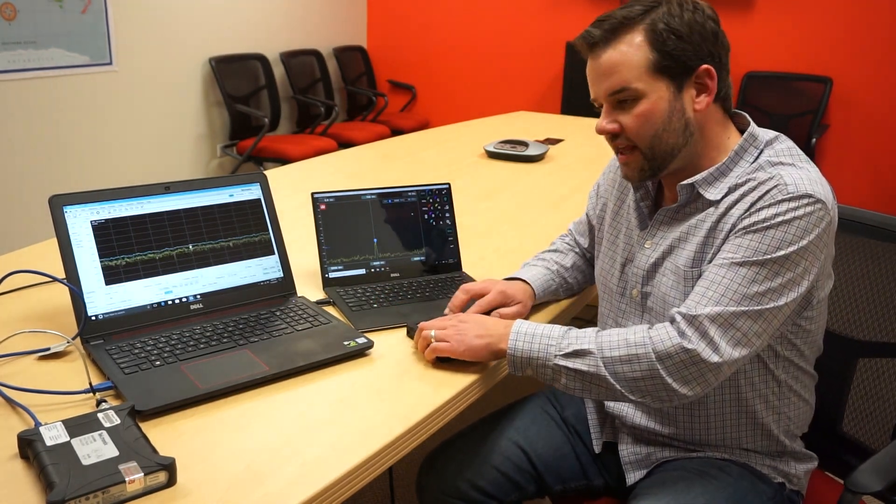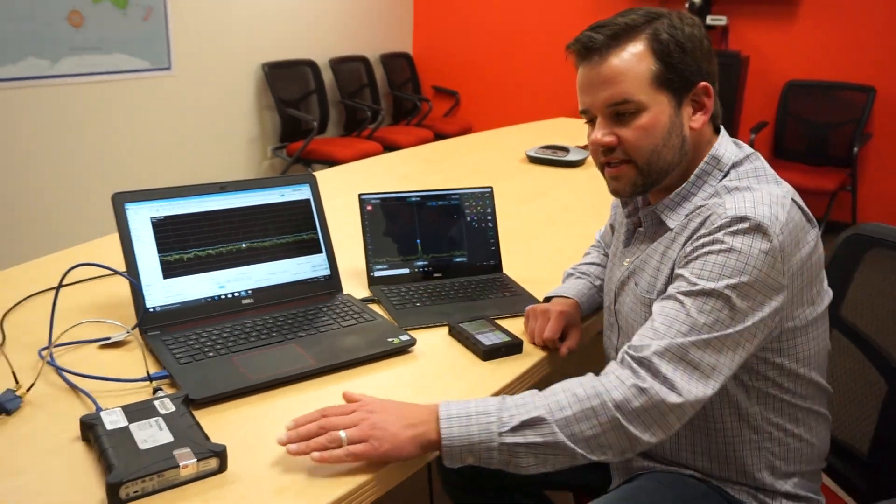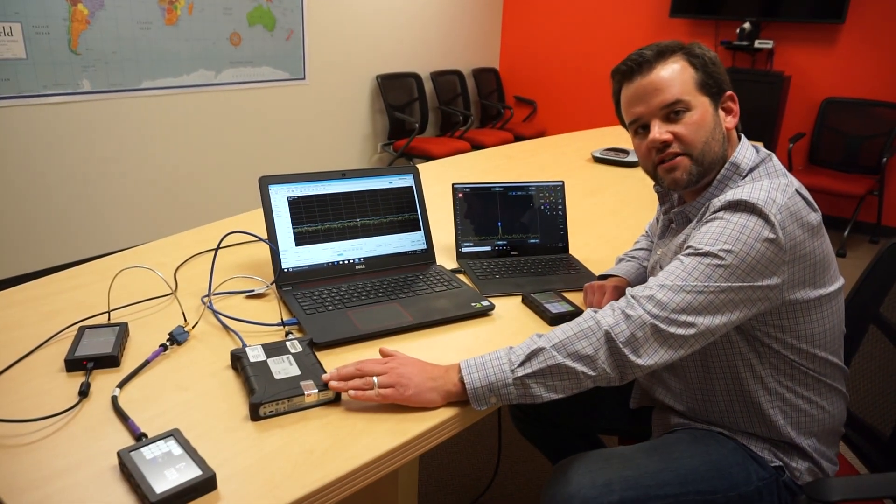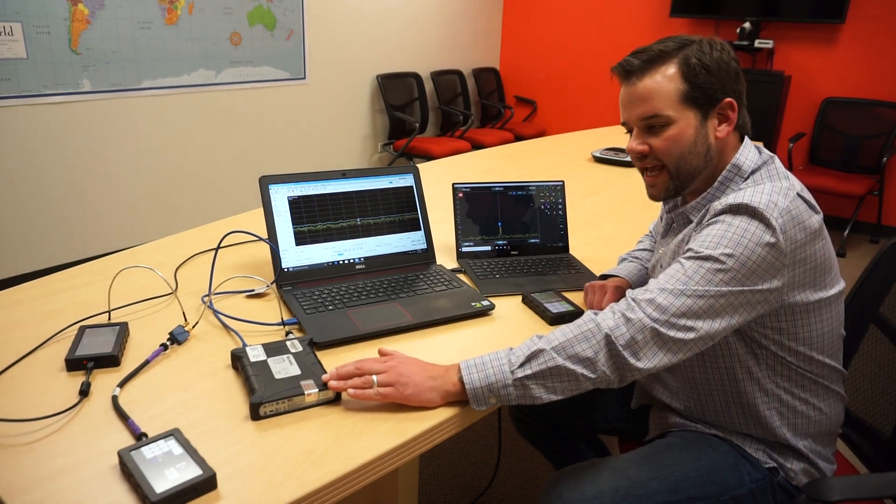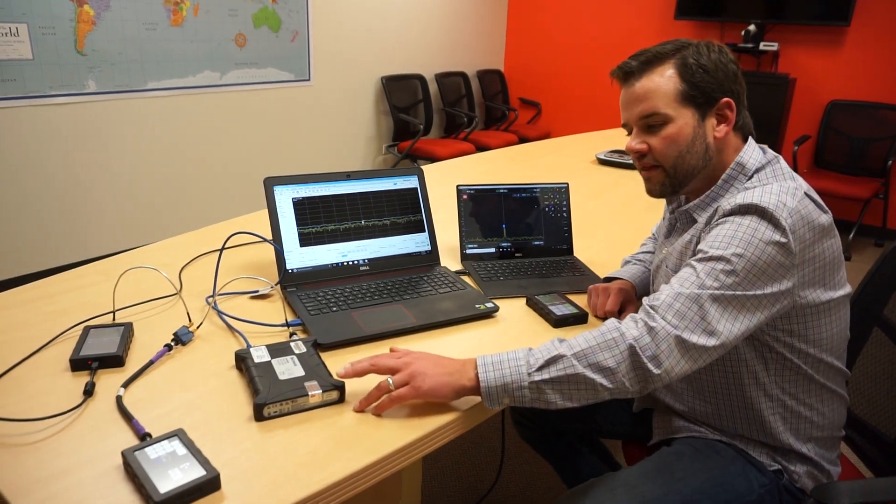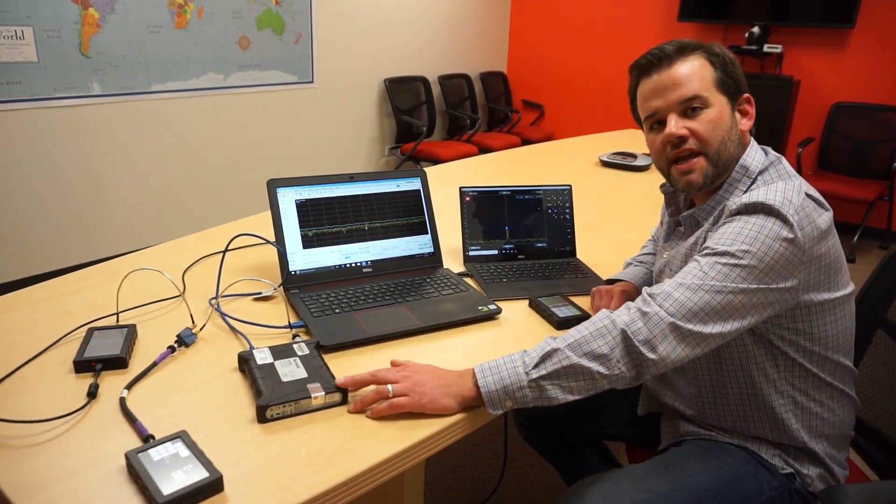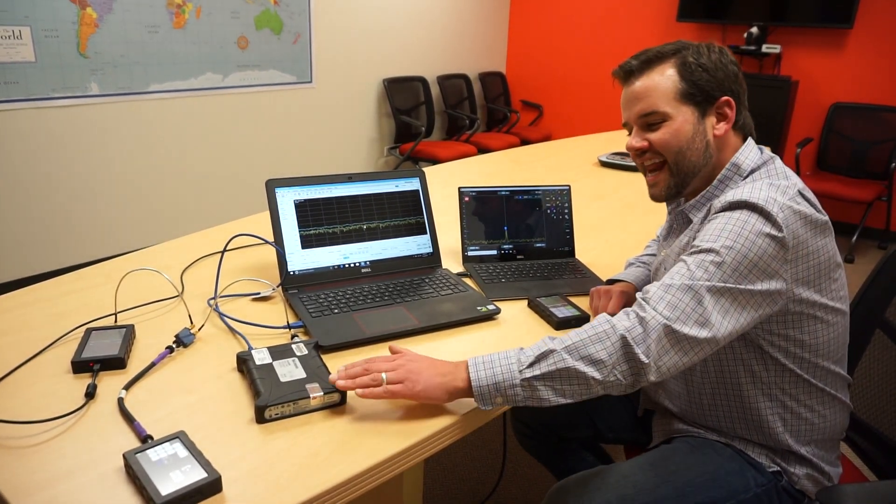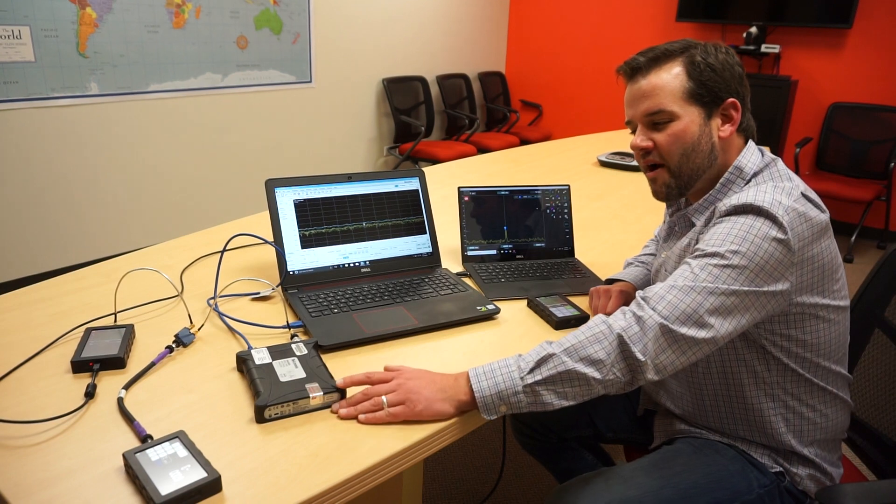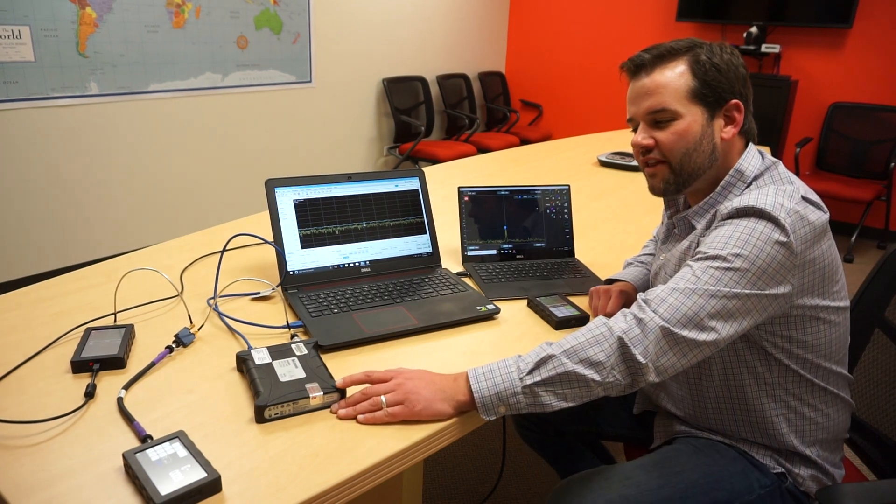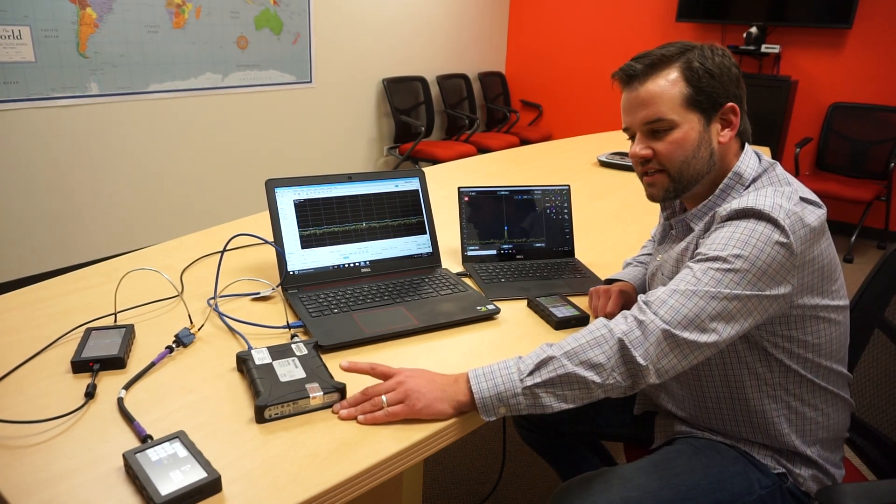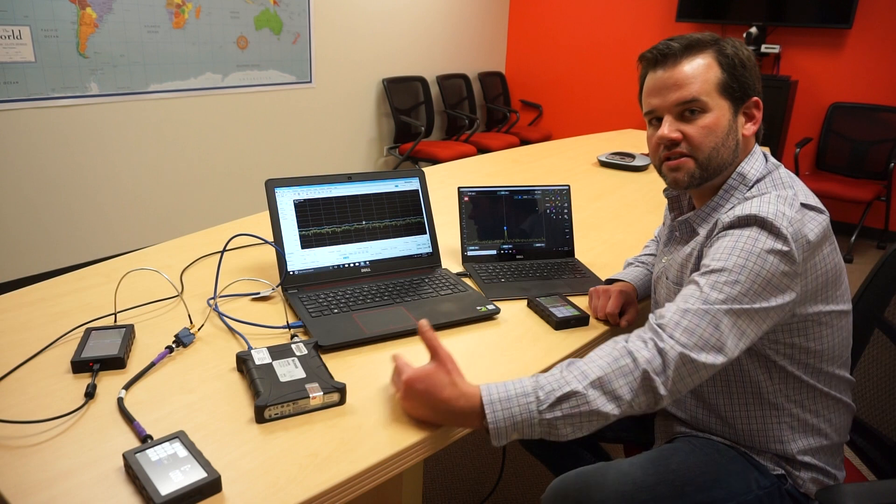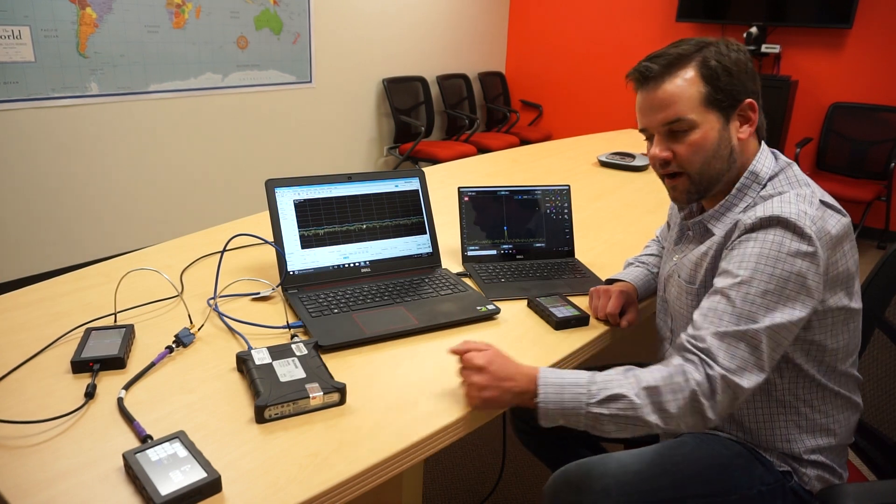We're going to look at these versus the Tektronix RSA306B. This is a USB-driven spectrum analyzer. It has been on the market for roughly a year and actually has a range of 9 kilohertz on up to 6.2 gigahertz.